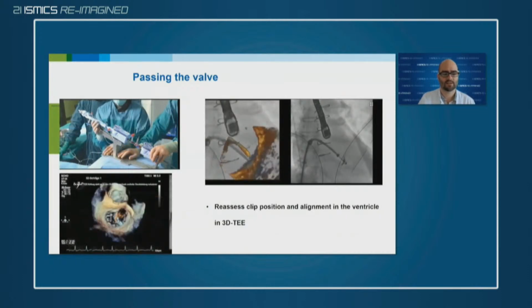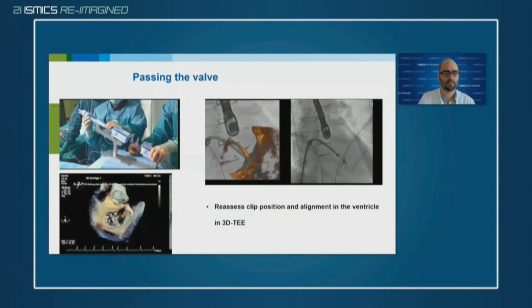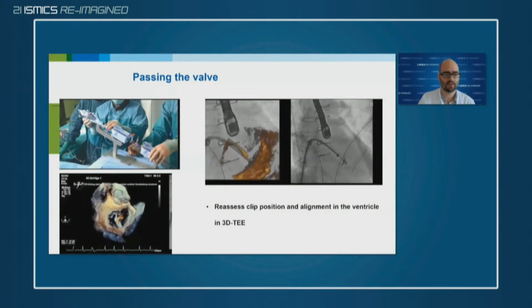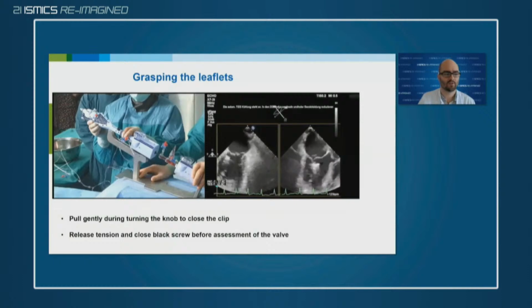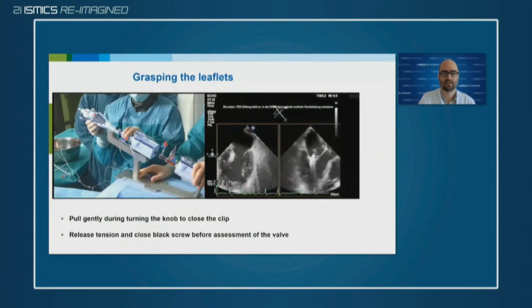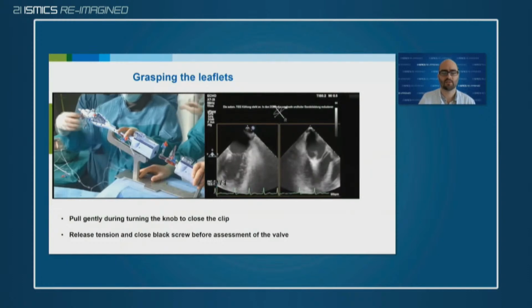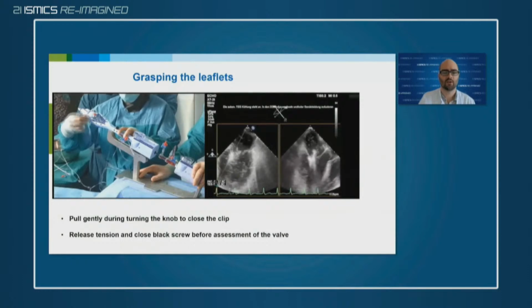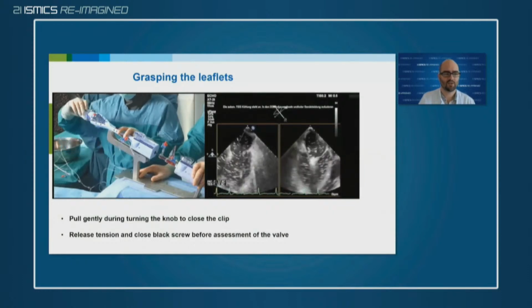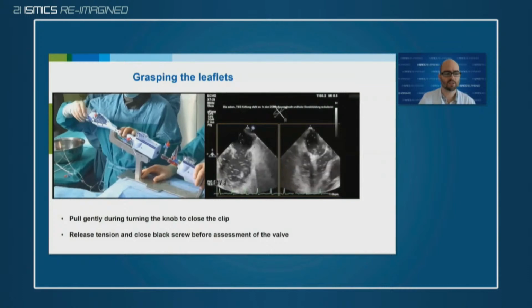You have to reassess the clip position because by touching the leaflets, of course, the alignment of the clip can change. So be sure to reassess the clip position after passing the valve. If you have a proper position, you can start the placement of the clip and the grasping of the leaflets. So you slightly pull on the whole system until the clip is located just below the leaflets, until the leaflets are located on the clip arms, and then you can lower the grippers.